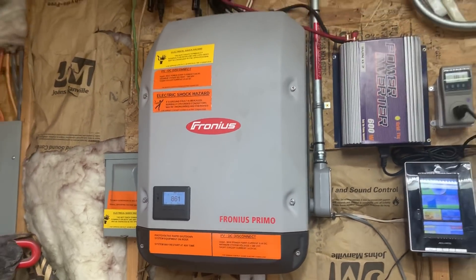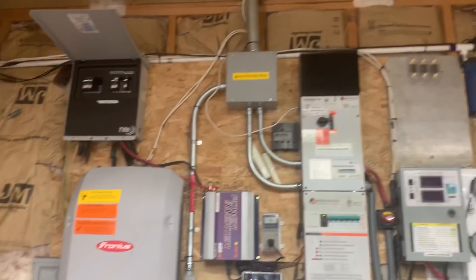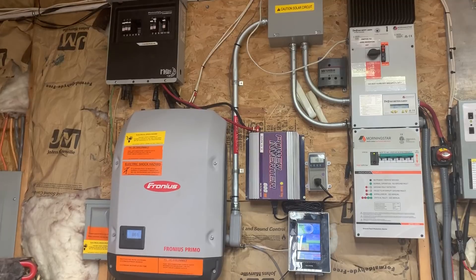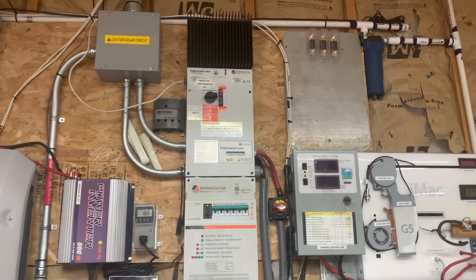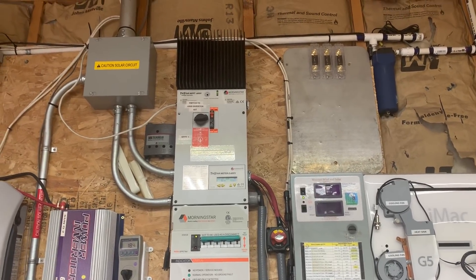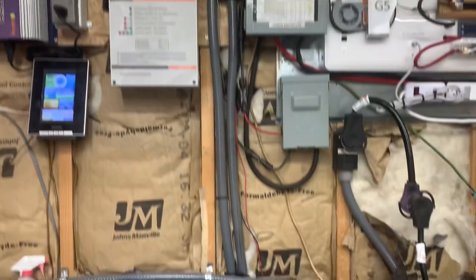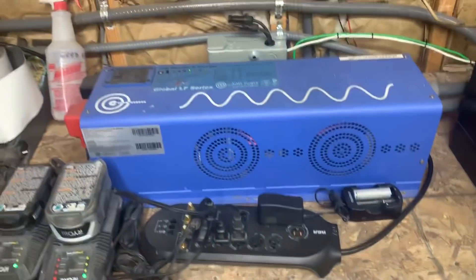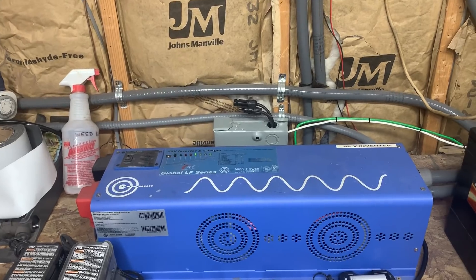If I were to lose power and the grid goes down, the solar panels shut down and the Fronius inverter shuts down — so we can't shock anybody working on the electrical lines. In that case, I can flip this switch on the Morningstar charge controller transfer switch, and now the solar panels will come in and instead of passing through to the inverter, it passes through and comes down into my battery bank. The battery bank powers this 1000-watt AIMS Power inverter, so I'll have power if the grid goes down.